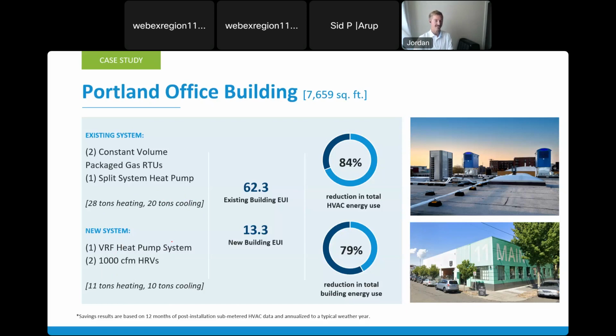So I mentioned the right sizing. This is not a unique example. Almost half of the buildings in our demonstration projects, when they converted to very high efficiency DOAS, were able to cut their system capacity in half. So 20 tons of cooling down to 10 tons of cooling. Obviously, this previous building was significantly oversized, but by eliminating most of the ventilation load with these heat recovery ventilators, and by switching to a zonal heating and cooling system instead of a single zone system, we were able to significantly reduce the capacity of the system.